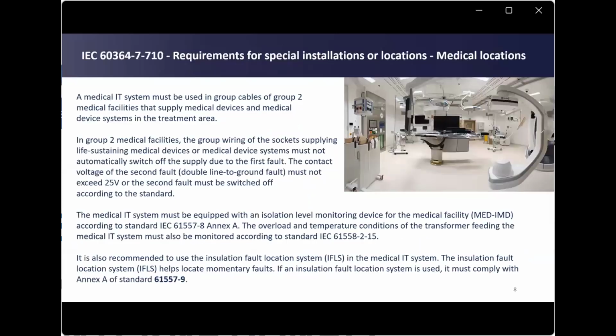What are the IEC 60364-7-710 requirements for special installations or locations, meaning medical locations? A medical IT system must be used in the group cables of Group 2 medical facilities that supply medical devices and medical device systems in the treatment area. In Group 2 medical facilities, the group wiring of the sockets supplying life-sustaining medical devices or medical device systems must not automatically switch off the supply due to the first fault.